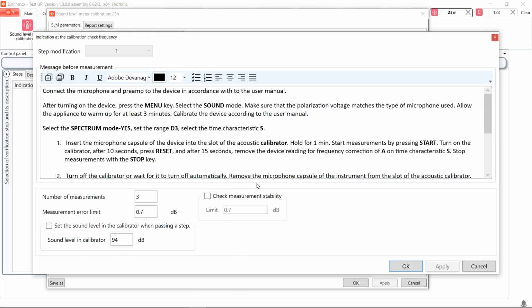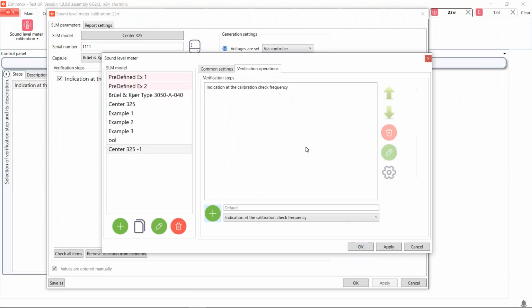And every time you click on this button, you can see the guidelines of what you need to do to perform the calibration procedure. And here we will set some of the parameters. So number of measurements is 3. Measurement error limit 0.7 decibel. Sound level in calibrator 94 decibel. So let's press OK. Now you can see that the first step was added to the procedure of calibration, and let's perform it. So we press apply and OK.